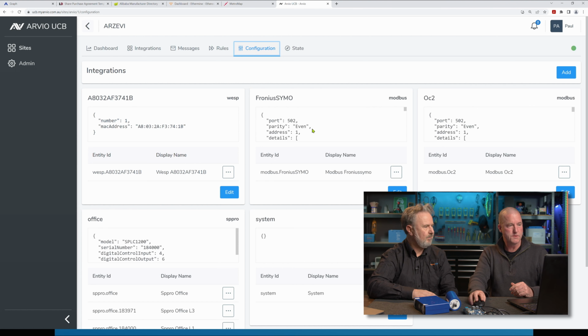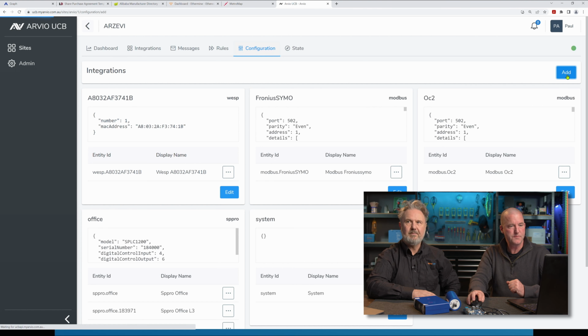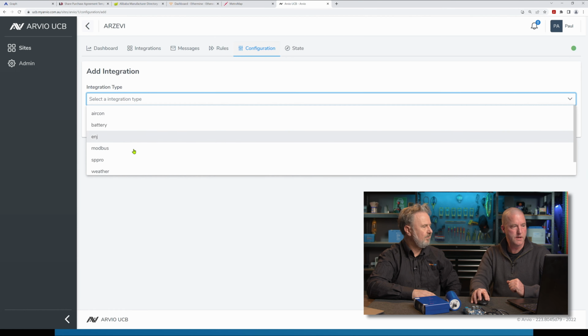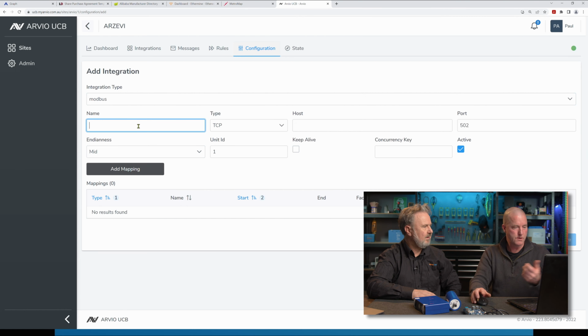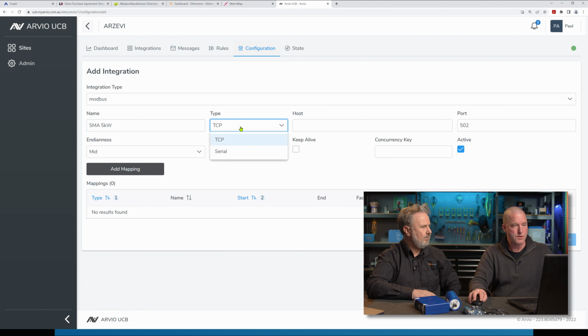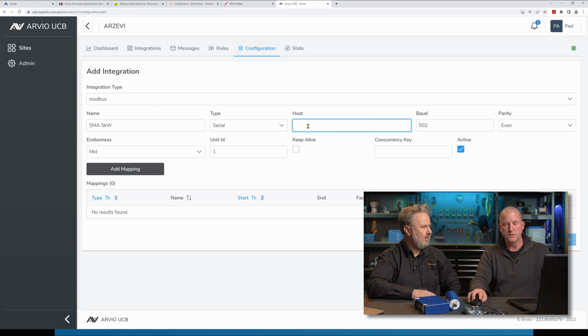Then you go up to configuration and say add. What type of device do you want to add? A Modbus device. I'll call it an SMA inverter, let's say 5 kilowatt, and I want to communicate Modbus via serial. The host script is one that you can extract from the USB stick when you plug it in, because any brand of USB stick needs to be communicated with by this PC. So we sell this particular one because we've tested it and written a script inside here.